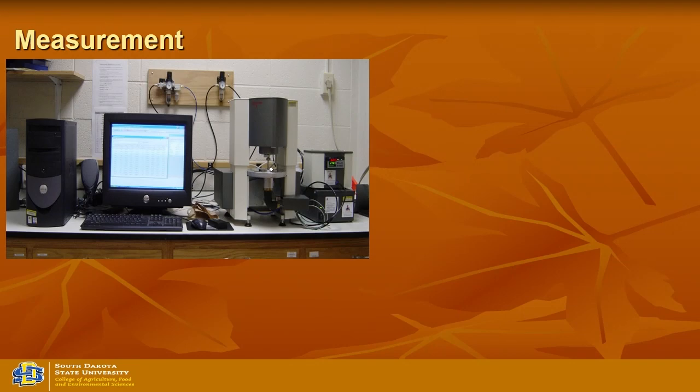This instrument is a constant strain equipment, so you apply strain, get the stress output, similar to what Sushil has in his lab. Strain input, stress output. Correct? Yep.